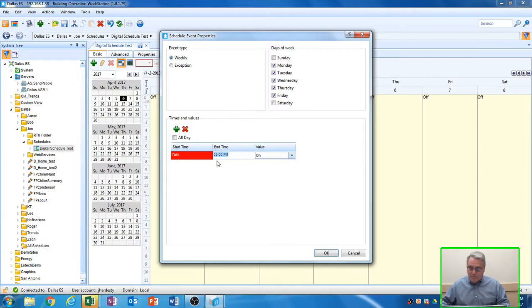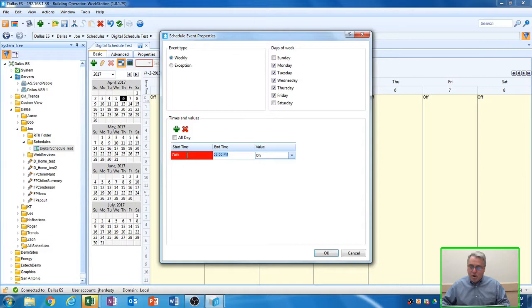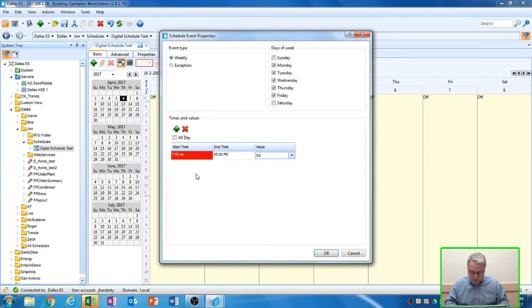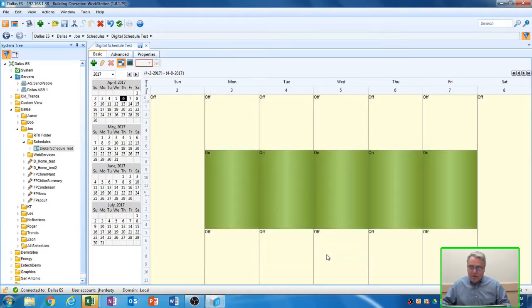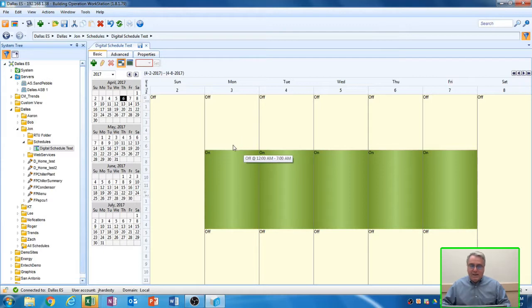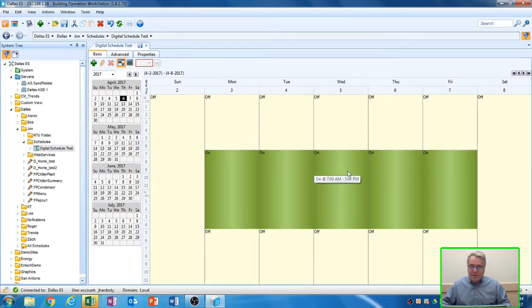The end time I will leave at 5 p.m., and the value is I want the schedule to be on during that time frame. You notice it turned this box red over here, and it said the entry must be in the proper format. So let's type that in properly. It should be 7-0-0 a.m. Type just like that. I select it on and select OK. Now you'll see it automatically enters into your schedule Monday through Friday 7 a.m. to 5 p.m. on your schedule.